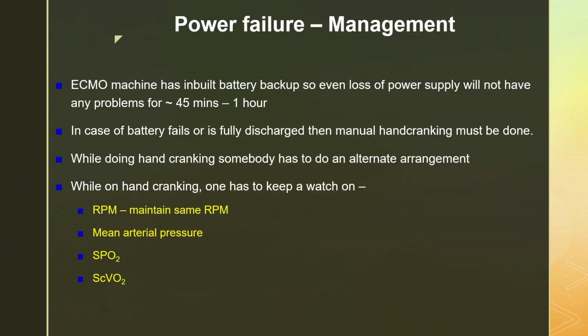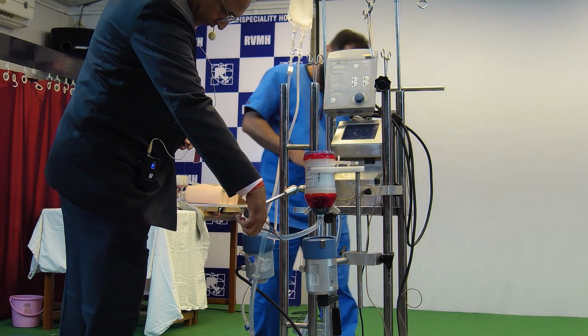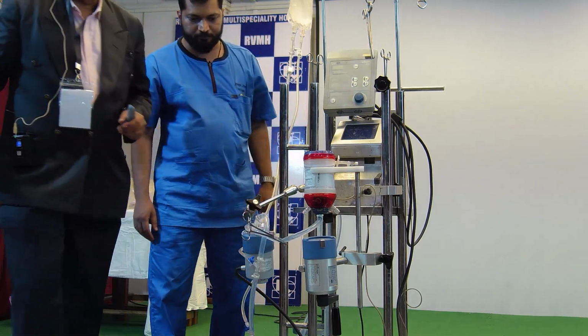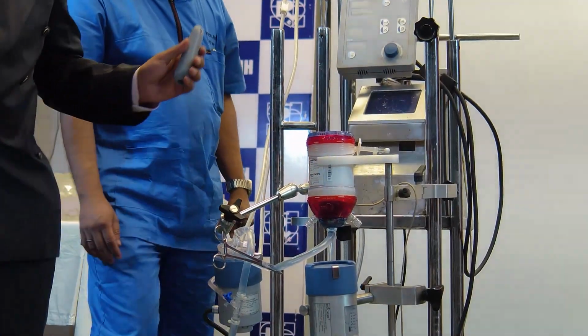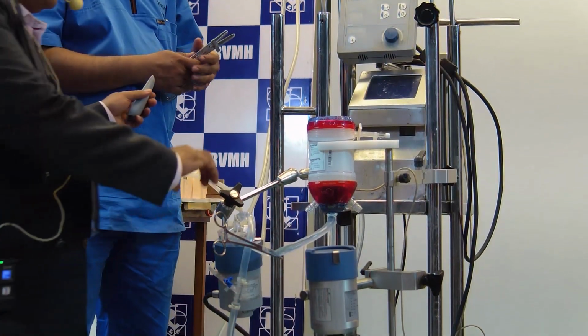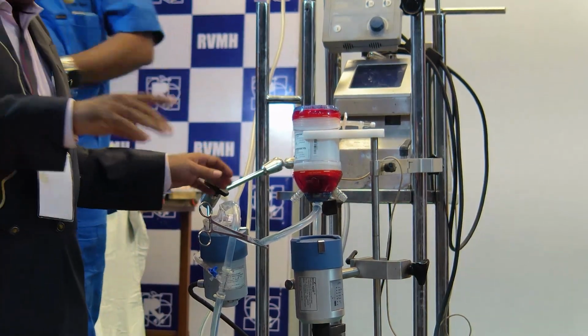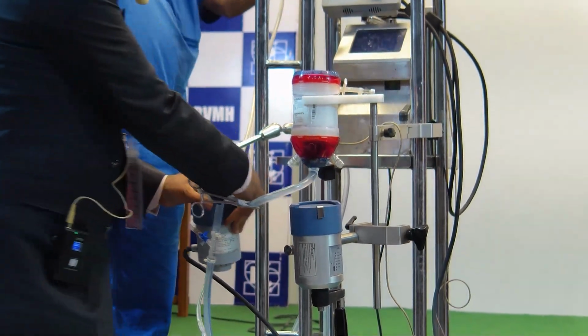First thing, suppose the machine stops suddenly. Upon the machine stopping suddenly, first always put the clamp in the return line. That's the first step. When I say return line, it can be anywhere in the return line, after the pump, anywhere. Then take the pump out.